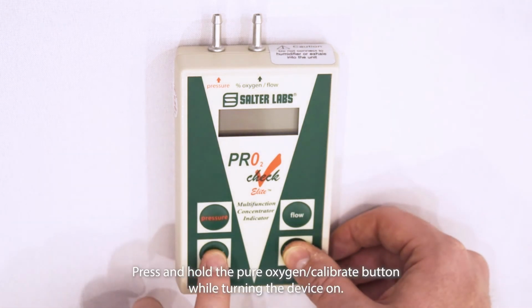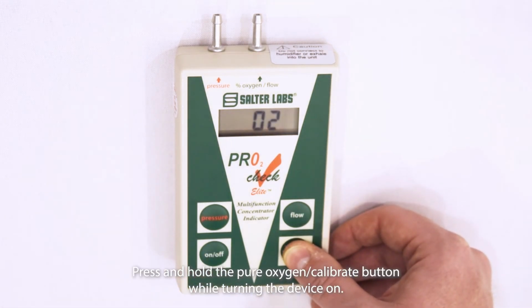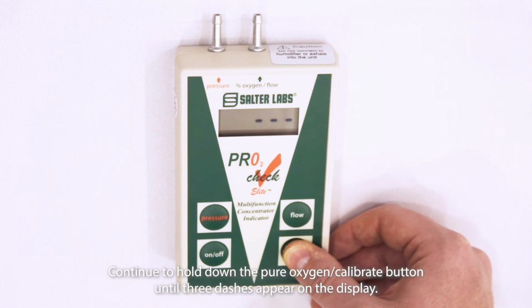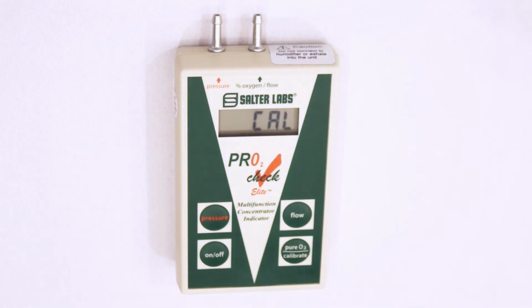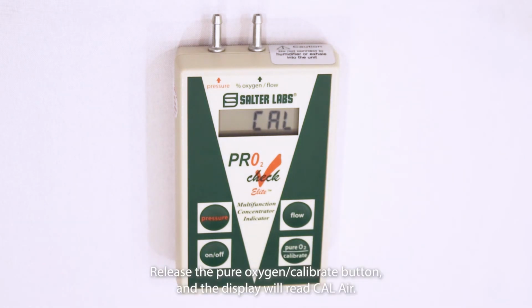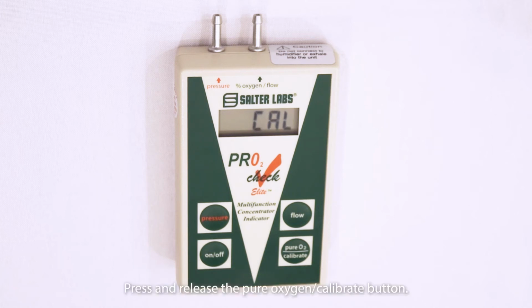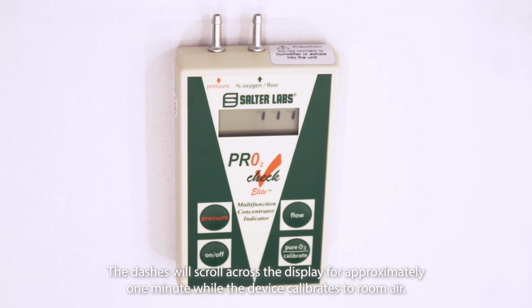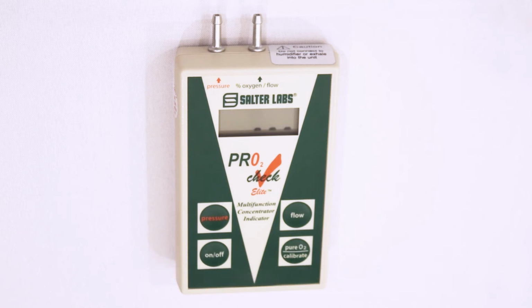Press and hold the Pure Oxygen Calibrate button while turning the device on. Continue to hold down the Pure Oxygen Calibrate button until 3 dashes appear on the display. Release the Pure Oxygen Calibrate button and the display will read Cal Air. Press and release the Pure Oxygen Calibrate button. The dashes will scroll across the display for approximately 1 minute while the device calibrates to room air.